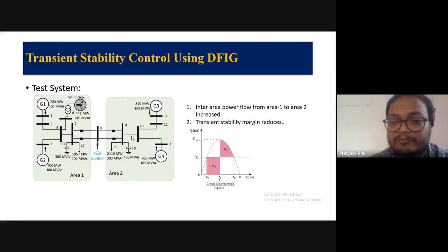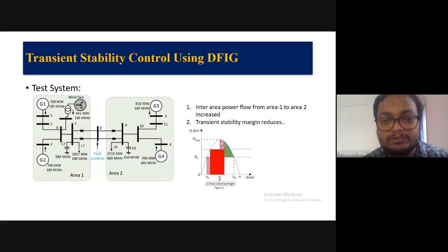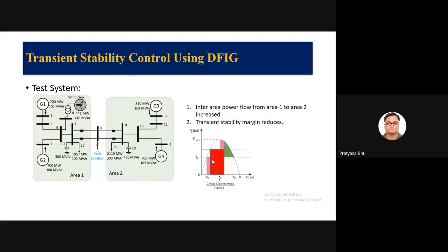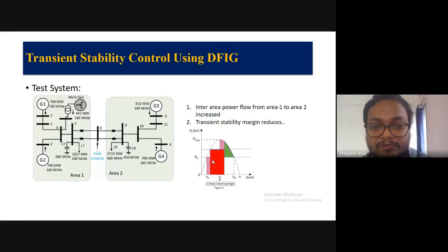Now as it increases the inter-area power flow, if you remember the equal area criterion, the accelerating area A1 has to be equal to or less than the decelerating area A2. So when you have more inter-area power flow, your initial condition changes, and you can represent any system for transient stability study. If one group of generators becomes unstable from the rest group of generators, you can represent it with this. So here generators 1 and 2 are going to be unstable from 3 and 4. Now generators 1 and 2 you can represent with one generator, and 3 and 4 with an infinite bus. So basically the angle difference between generators 1, 2 and generators 3, 4 is equivalent to the single machine infinite bus.